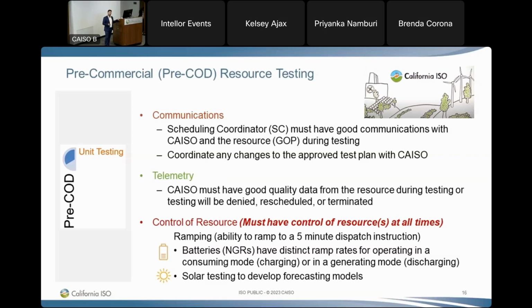Coordinating any changes approved to the CAISO, we'll have sites where we see the test plan, we've gone through D2, D1. The scheduling coordinator calls that day and says, hey, we want to test today. It's like, okay, per your OMS, everything looks good, go ahead and test. Say for instance they have a charge of 200 megawatts they're testing, and we start getting close to peak, hour ending 20. Meanwhile we're pulling load, we're moving generation, and all of a sudden they want to test 300 megawatts. Well, we see them in the control room, but we didn't get a phone call. We look at the test schedule, we didn't see that's what they wanted to do. So we call them and say, hey, what are you guys doing? Oh, we just wanted to test another hour.